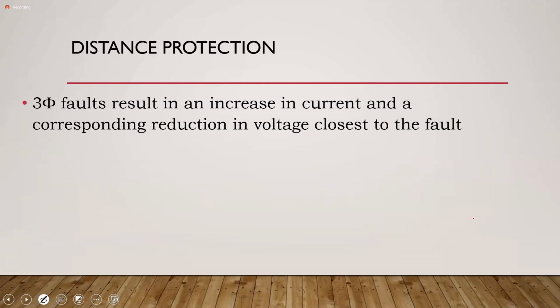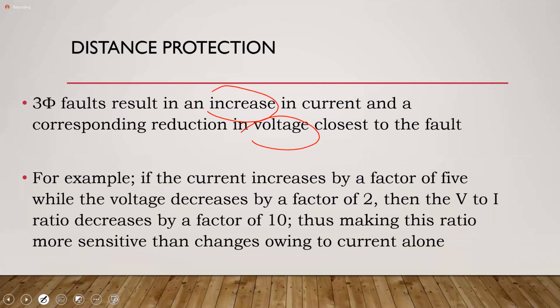for distance protection, yes, once you have a three-phase fault, you're going to have a reduction in your voltage, and you're going to have an increase in your current. So therefore, the ratio of voltage to current will be reduced. Remember we spoke about the balance beam? Yes? So when you have the two coils exerting a force and they are equal, yes, that would be the set point.